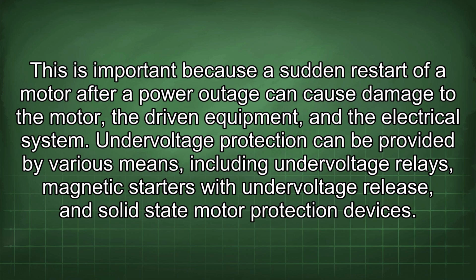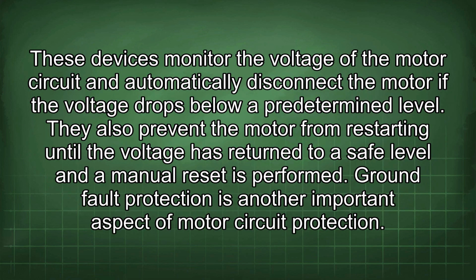Undervoltage protection can be provided by various means, including undervoltage relays, magnetic starters with undervoltage release, and solid-state motor protection devices. These devices monitor the voltage of the motor circuit and automatically disconnect the motor if the voltage drops below a predetermined level. They also prevent the motor from restarting until the voltage has returned to a safe level and a manual reset is performed.